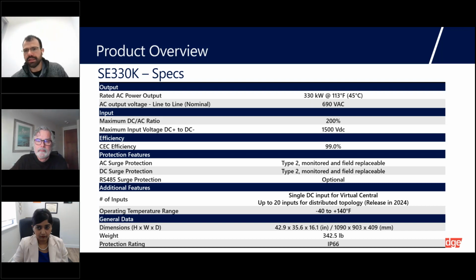One thing that we're also excited about is that this inverter has two options to start with. It's a DC single input, so it's great for virtual central applications where you're clustering all the inverters together to reduce DC cabling and the balance of system. Right now it's single DC input. Later on in 2024, there will also be an option for up to 20 inputs for distributed topology if you want to place the inverter close to the array. It weighs about 350 pounds and has an IP66 rating for protection.